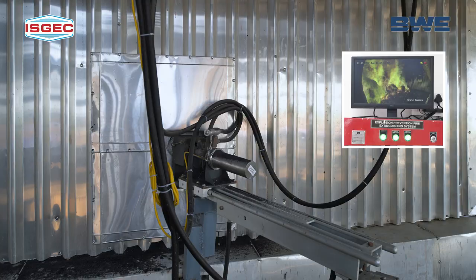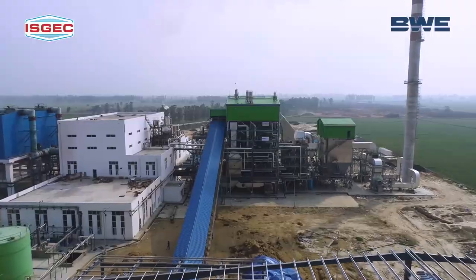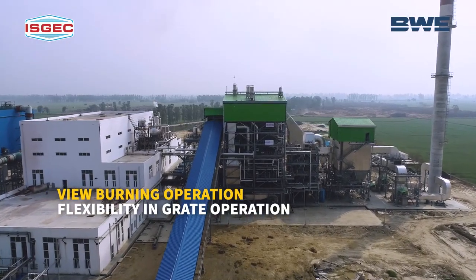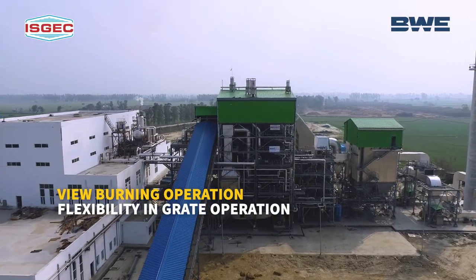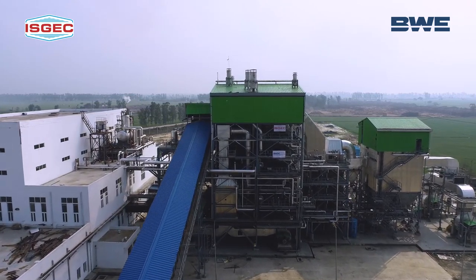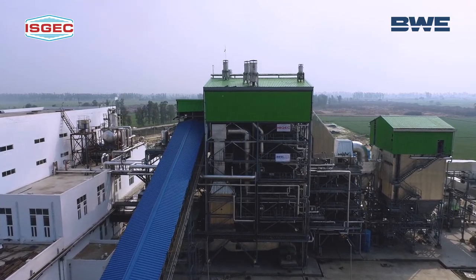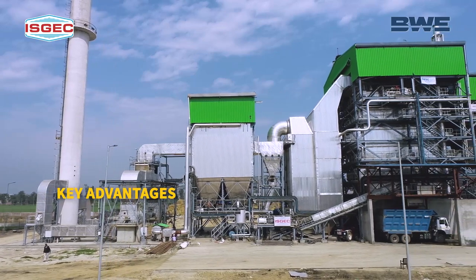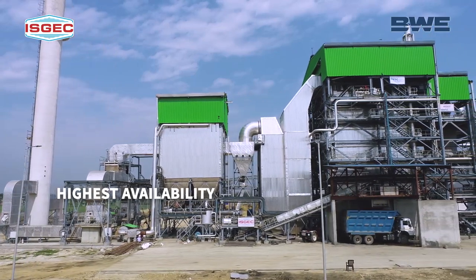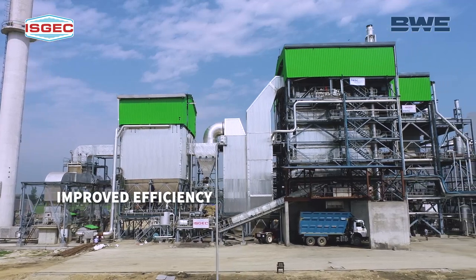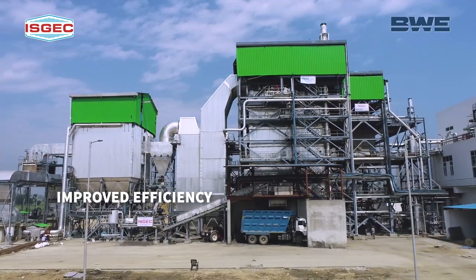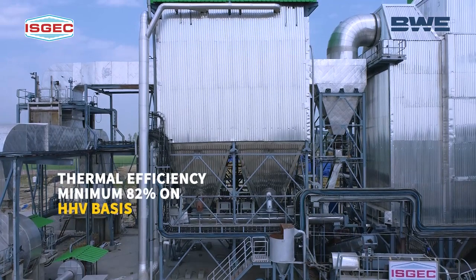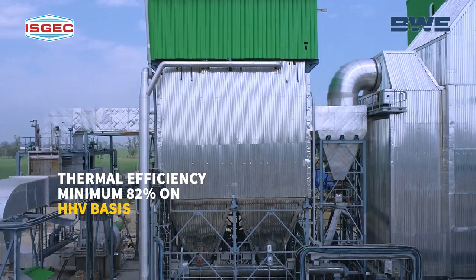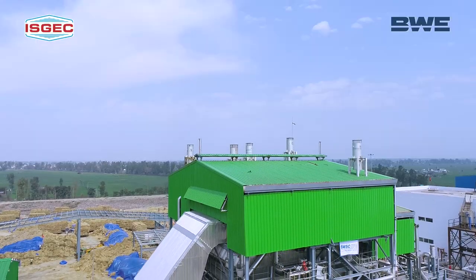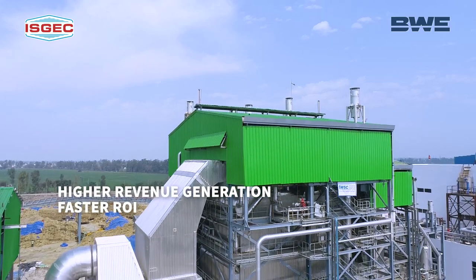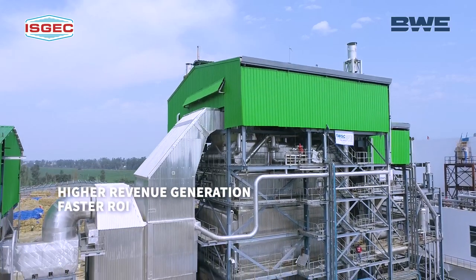The boiler is installed with a furnace camera to view the burning operation and provide flexibility in operating the grate as and when needed. This helps in better thermal efficiency. The key advantages of these boilers are highest availability and best thermal efficiency as compared to other boilers, offering a minimum of 82% on higher heating value basis. This ensures higher revenue generation and faster return on investment.